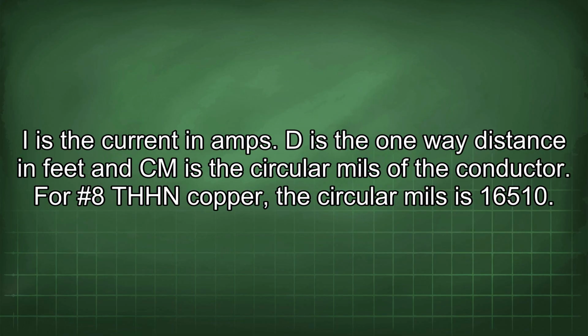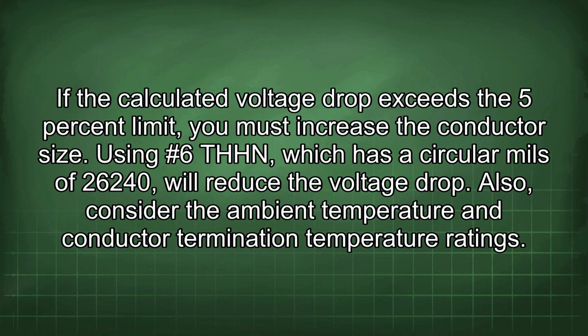I is the current in amps. D is the one-way distance in feet, and cm is the circular mils of the conductor. For #8 THHN copper, the circular mils is 16,510. If the calculated voltage drop exceeds the 5% limit, you must increase the conductor size. Using #6 THHN, which has a circular mils of 26,240, will reduce the voltage drop.